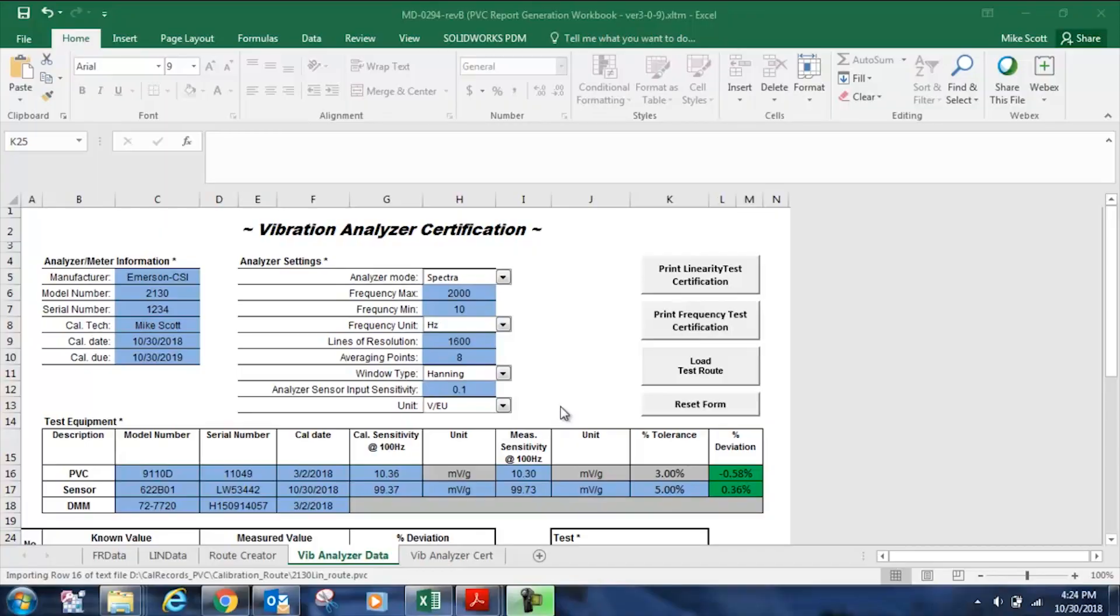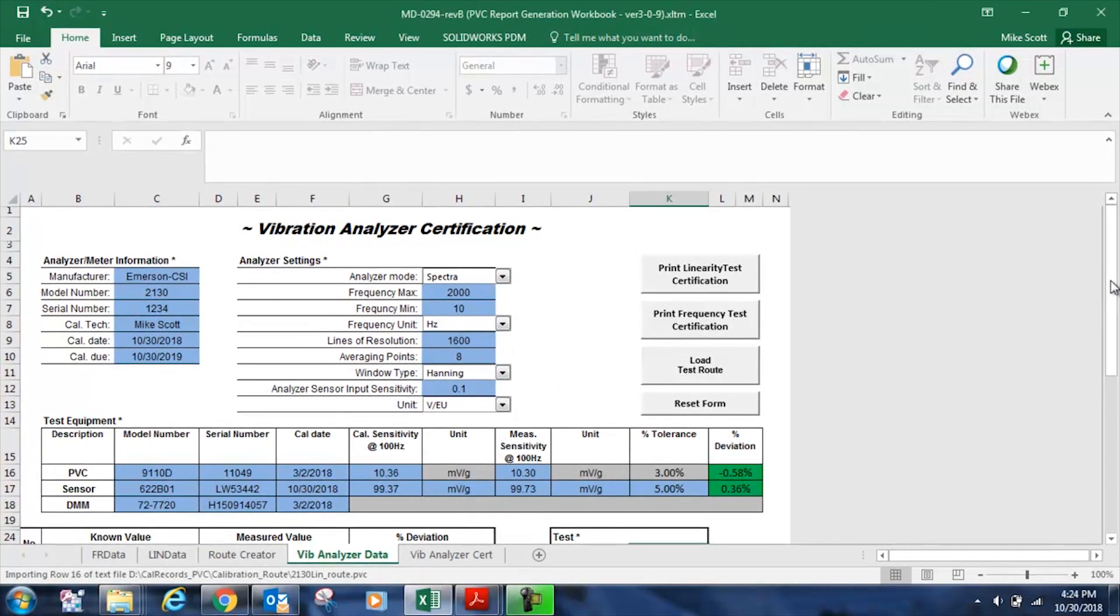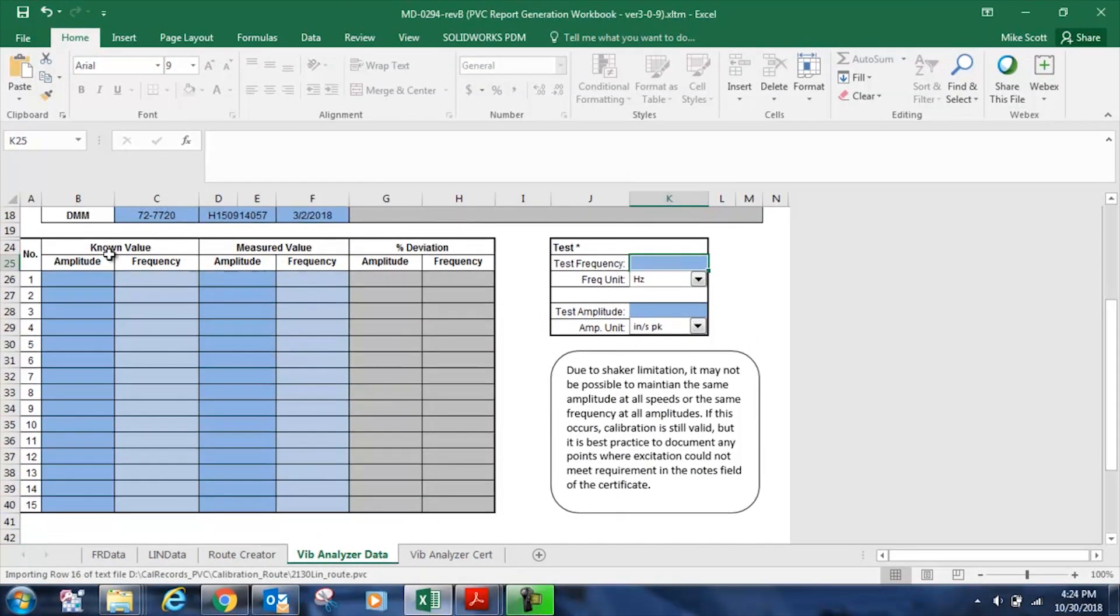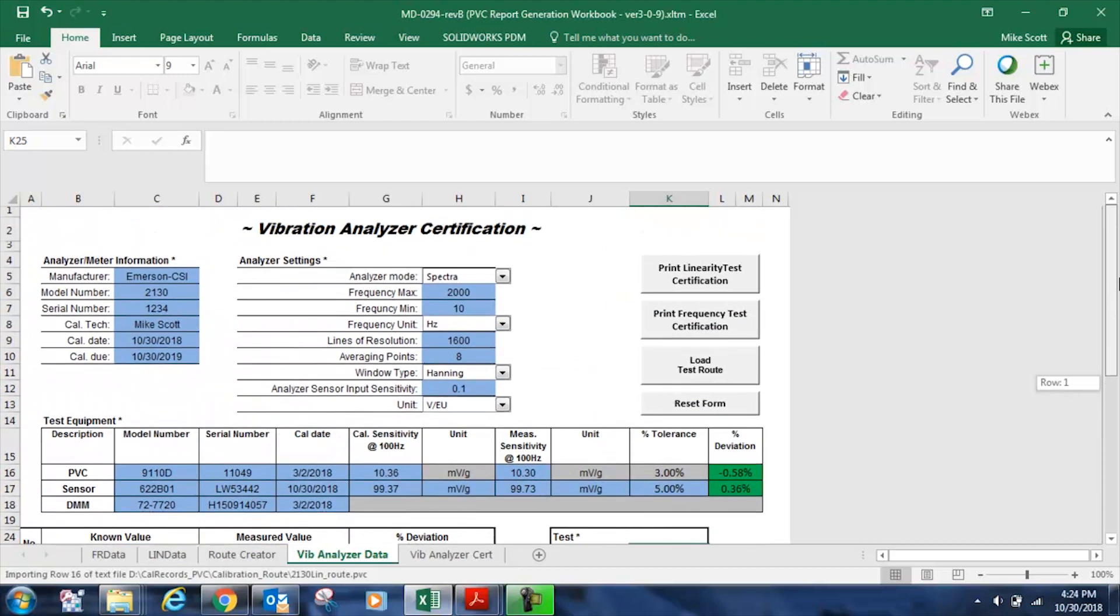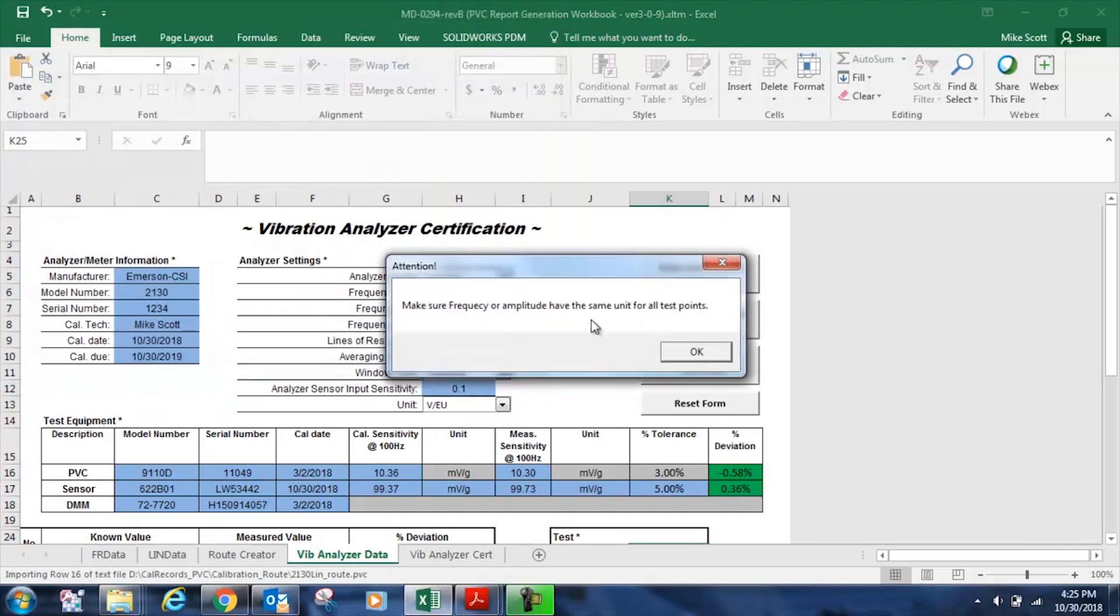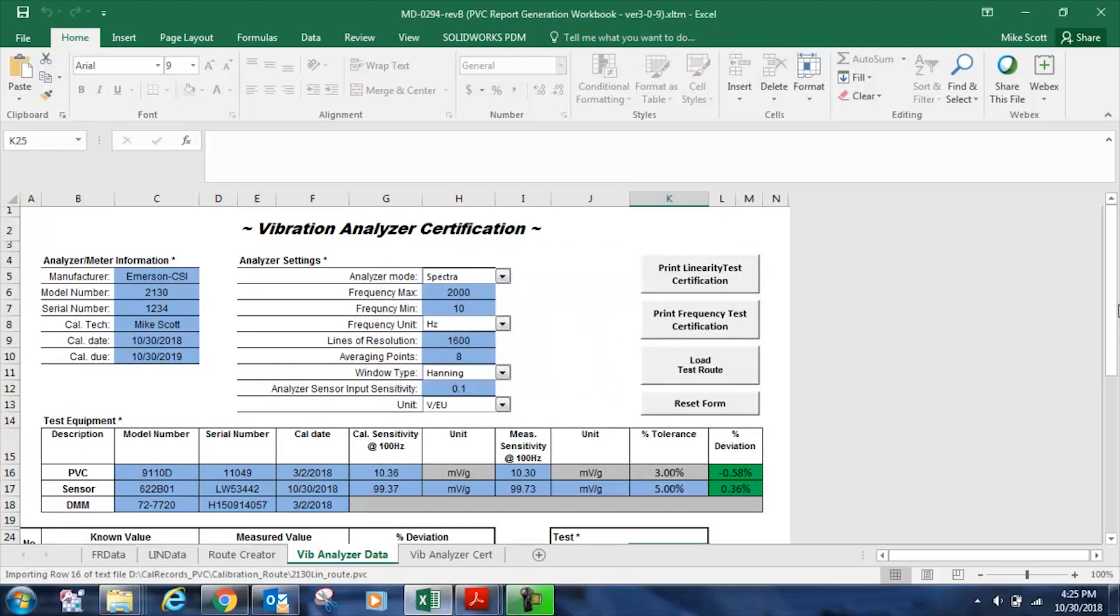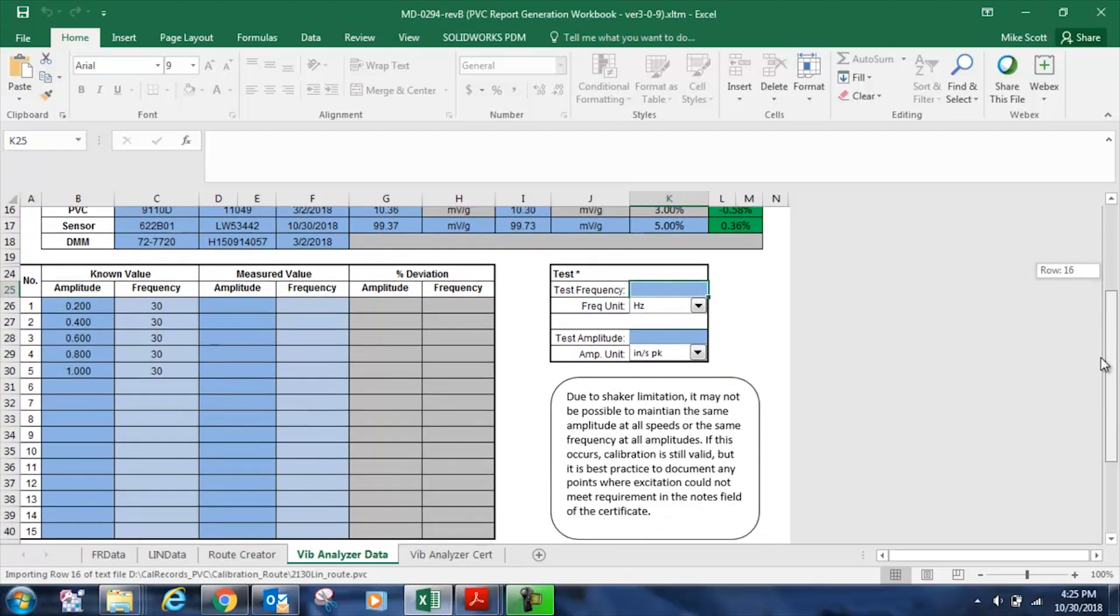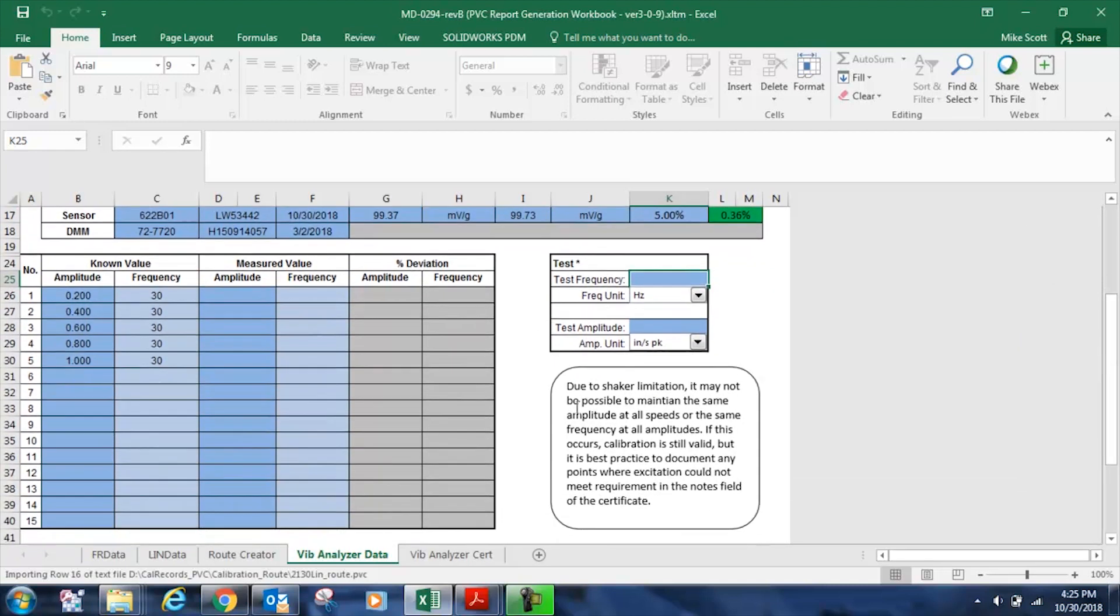Only one step remains to create the linearity test certification for my 2130. I need to enter the known and measured values from my test down here at the bottom of the certificate in the workbook.